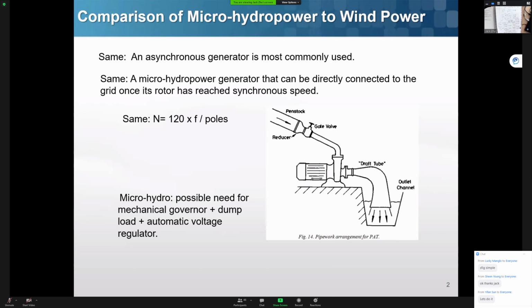But if you only require 1 kilowatt of power, like the example we gave you before, you will have something, usually an electrical space heater or electrical water heater. You will just put that actual 4 kilowatts to those space heaters or water heaters. So you will keep the generator running at the maximum speed. It's not going to vary in speed too much, because if the speed varies, you're going to change the voltage and the frequency.